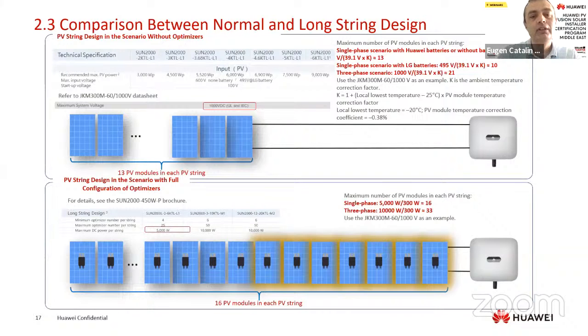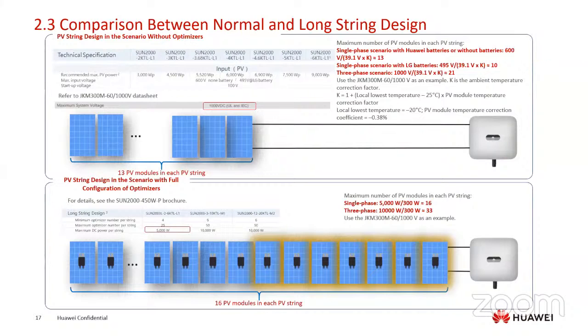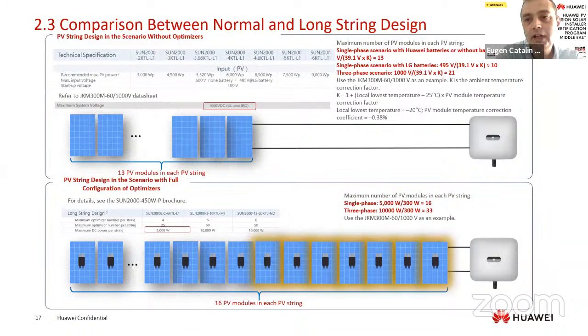Okay, as I said before, using the new optimizer type, we can install inverters in a long string design. What does this mean? This long string design configuration is available only in a full optimizer configuration. So we have here some examples using this panel, JKM300M. We take this as an example. So the numbers here are not standard. What is standard is that for an L1 single-phase inverter, you can install 5,000 watts per string, and for a three-phase inverter, you can install 10,000 watts per string. So these two values are standard. The rest depends on the panel, of course. So let's see some examples.